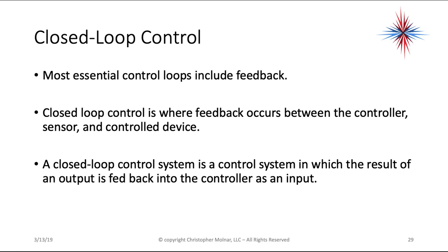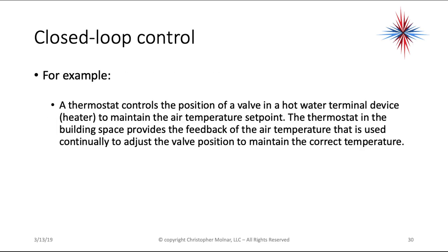Closed loop control is where feedback occurs between the controller, sensor, and control device. It is the control system in which the result of an output is fed back to the controller as an input. An example is a thermostat controlling the position of a valve in a hot water terminal device to maintain air temperature at a set point — the thermostat provides feedback of air temperature that is continually used to adjust valve position and maintain the correct space temperature.